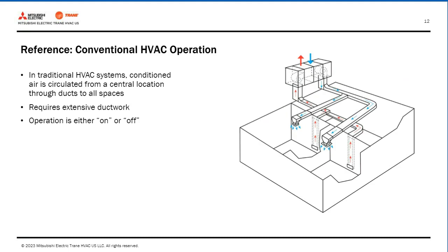So in contrast to VRF operation, conventional HVAC systems typically take a more centralized approach where ductwork is connected to a centrally located air handler, and there's large ductwork running out to different spaces. Some of the key issues with this is the more ductwork you have, the more potential for air leakage, which of course is directly related to your efficiency and your comfort within your space. When there is some sort of issue in the system, the extra ductwork can make it more difficult for contractors to find that leak and pinpoint the problem.